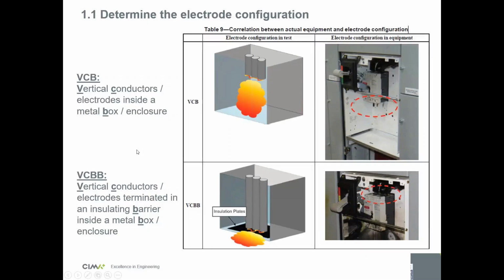Then VCBB is the same as VCB, vertical conductors inside a box, but it's also terminated in an insulating barrier. What's an insulating barrier? For example, the top of a molded case circuit breaker is in plastic. If you have a fault above the breaker, the source of the fault current comes from the upstream cable, and then the arc flash will be diverted towards the worker. It flattens on top of the breaker and is pushed towards the worker perpendicularly to the panel. So the arc flash doesn't go down inside the cell. It's flattened towards the person. In this case, the energy that the person is going to get is higher in VCBB than in VCB.